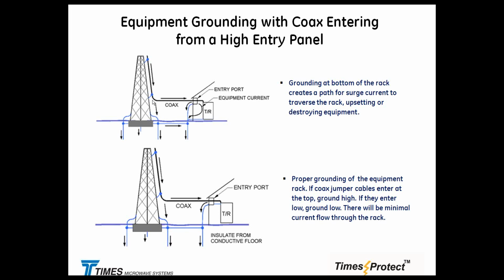One thing before I forget, if you are grounding the cable tray directly to the tower, okay, if you are bonding the end of the cable tray directly to the tower, please do not bond it to the master ground bar on the outside of the shelter or cabinet. You don't want to bring any more current into the shelter than you have to, or the grounding system for the site. So in most cases, people will be bonding the cable tray to the tower at this point, and they will be floating part of the cable tray right here. So the cable tray is only connected to one point of the structure.